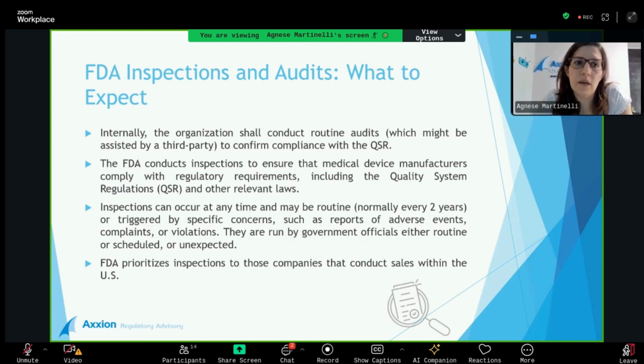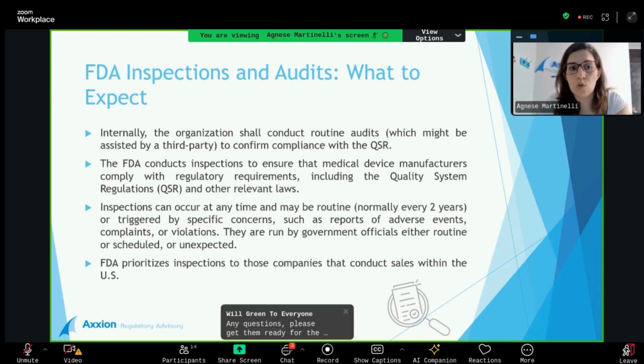What shall we expect about FDA inspections and audits? First of all, internally, each organization shall conduct routine audits, which might be assisted by a third party, and which are in general run in order to confirm compliance with the quality system regulation. On the other hand, the FDA conducts inspections to ensure that medical device manufacturers comply with the regulatory requirements we mentioned and other relevant laws.